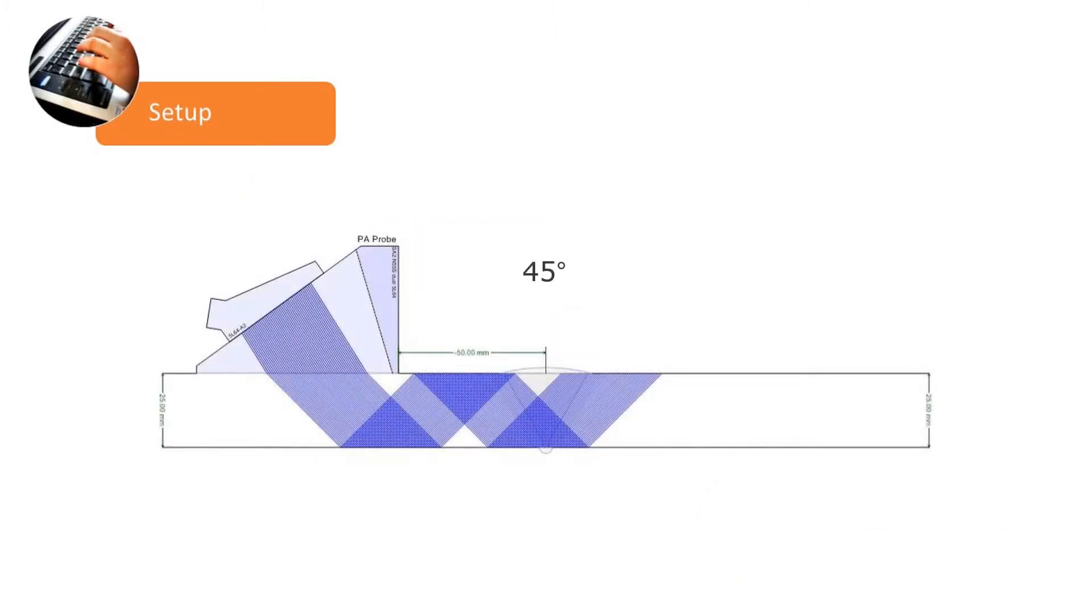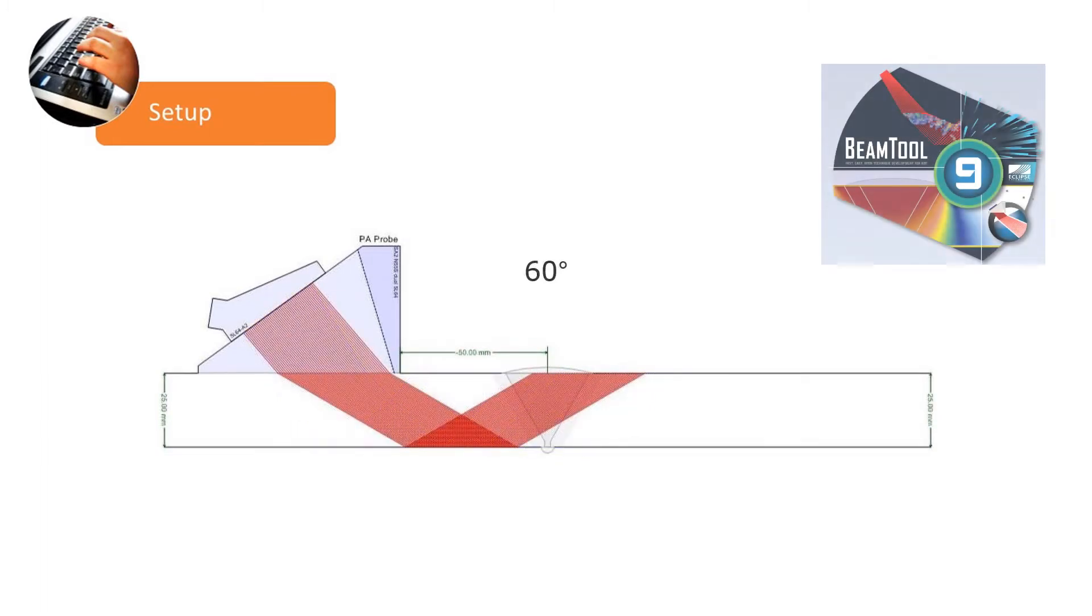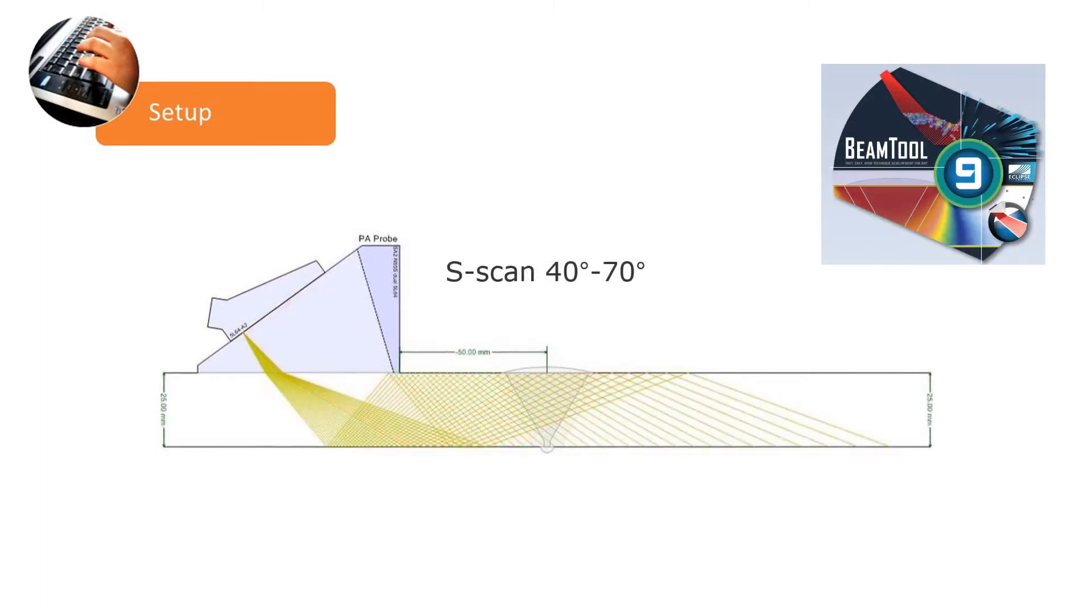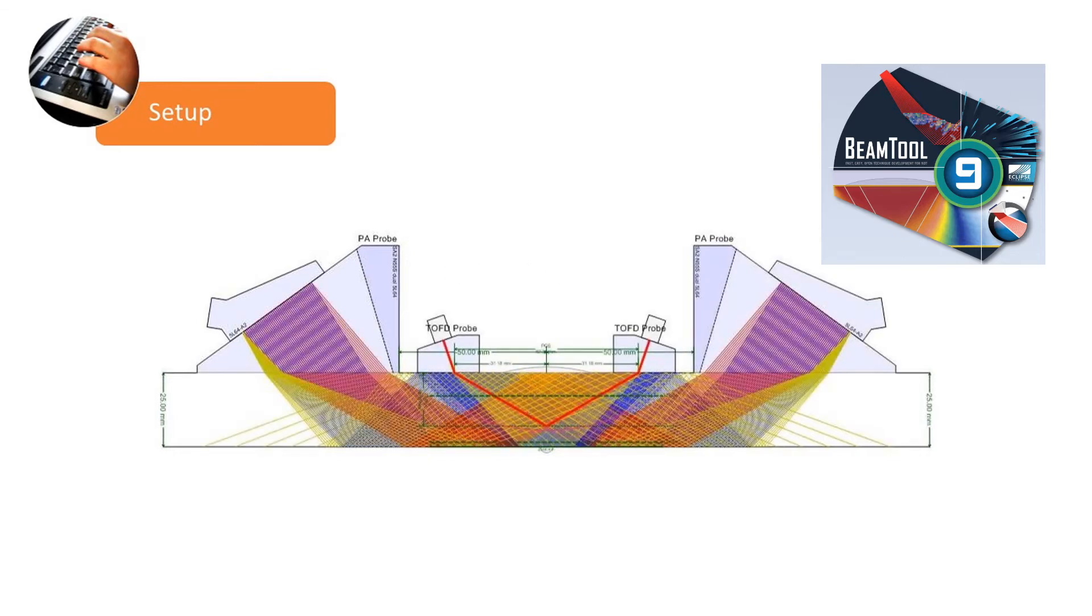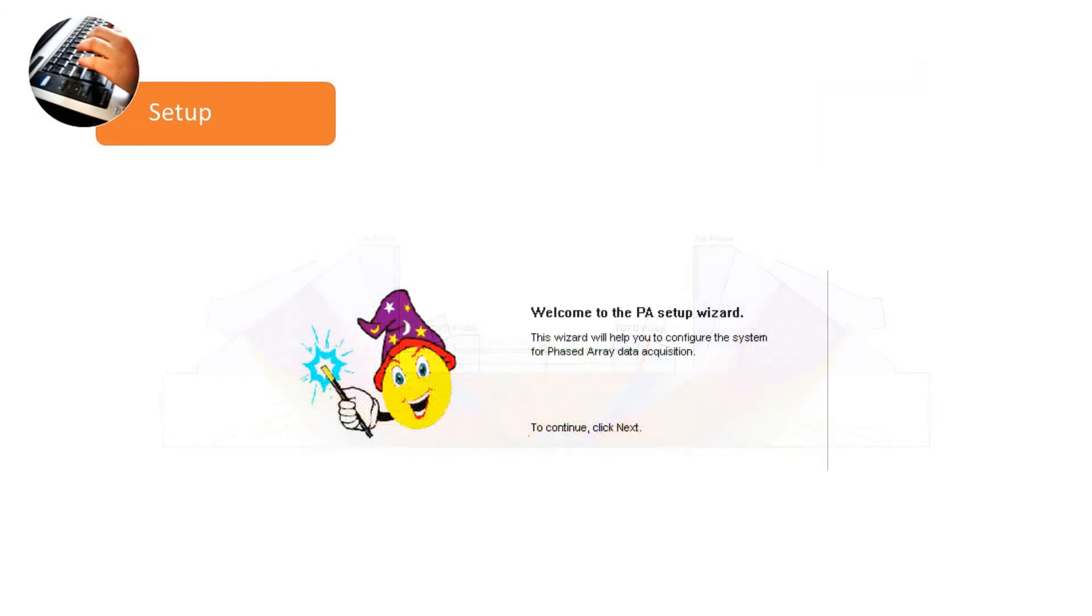Setup starts with an inspection plan known as a Scan plan. TDScan uses ES Beam tool to create a graphical computer environment in which the optimum inspection setup is determined and saved for repeatable use. Setup may also be done using wizards or manually.